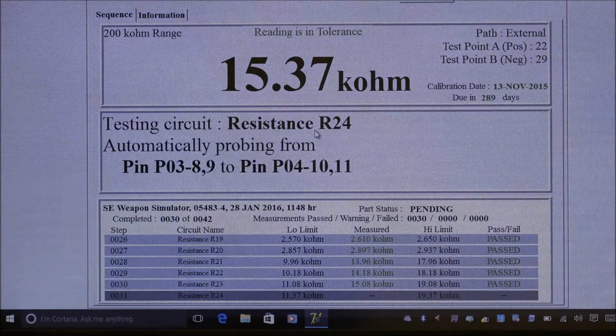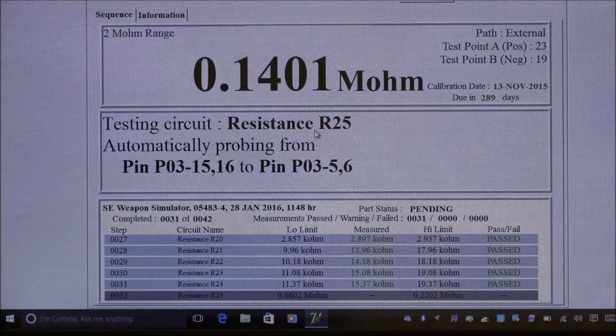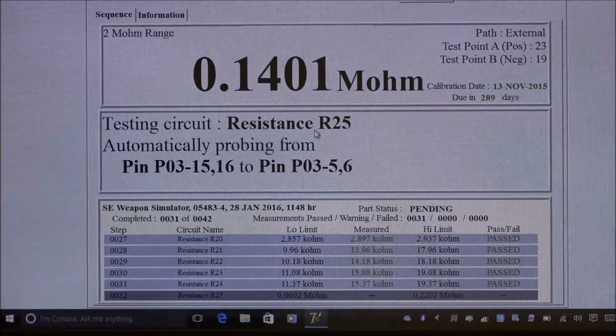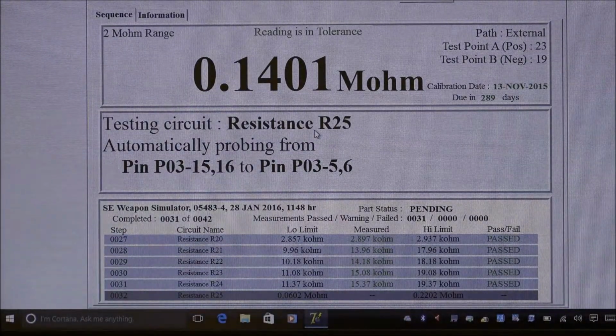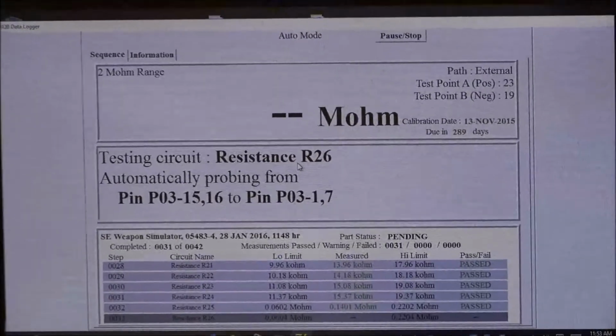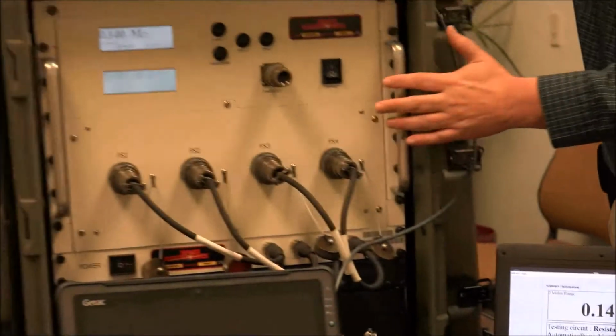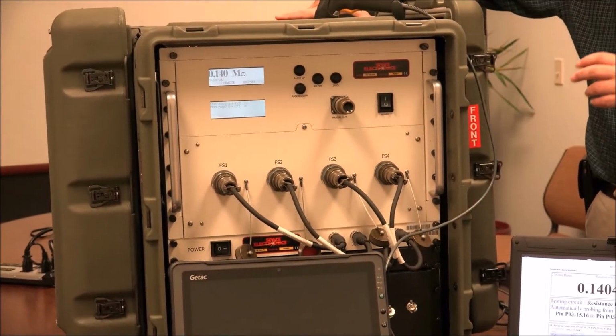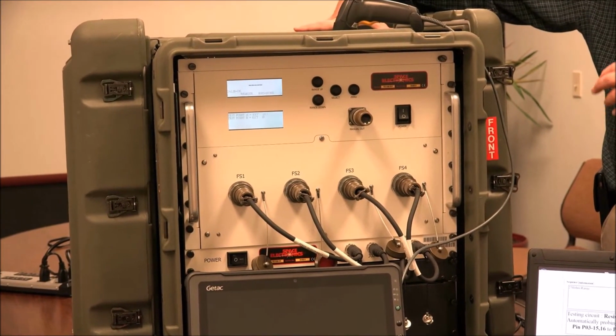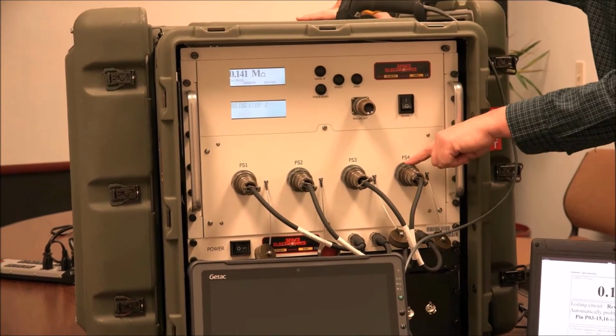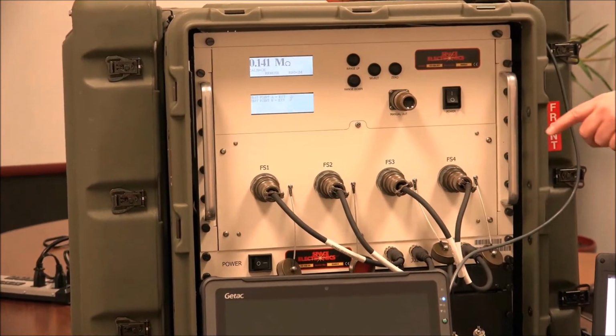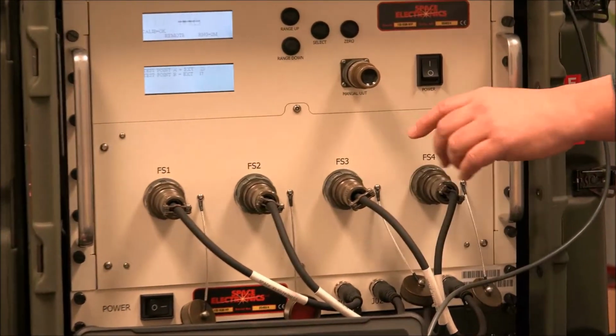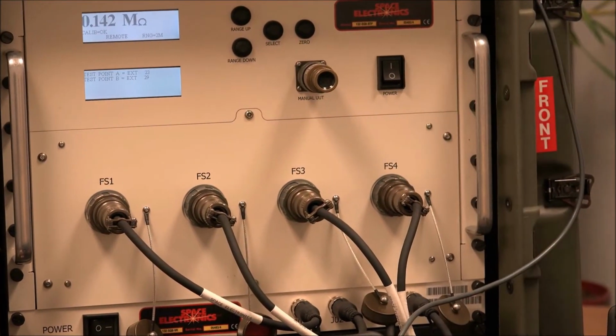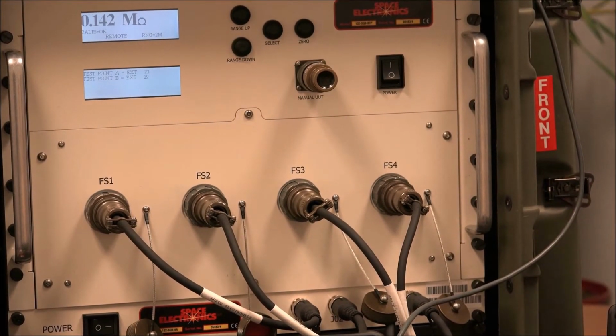While it's running, let's talk about fail-safe and test currents. We design our systems with a 10 milliamp fail-safe design. That means internally, if everything goes wrong and the maximum voltage DC in the tester is available at the fail-safe input, then the fail-safe path resistors will limit that to no more than 10 milliamps maximum. That's called the fail-safe current.